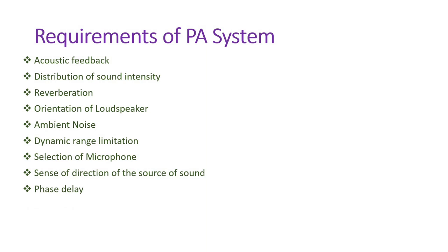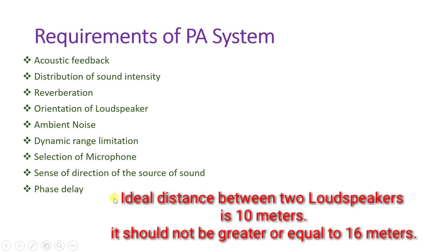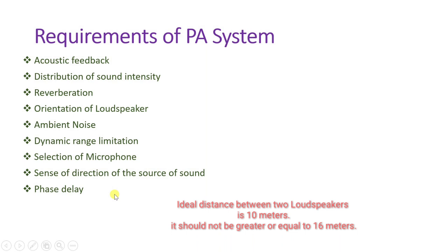Next is phase delay. Sound from the nearest loudspeaker may be heard together with sound from a loudspeaker at a greater distance, causing phase delay between the two sounds. To avoid this, loudspeaker separation distance should not exceed 16 meters. The ideal distance between two loudspeakers is 10 meters — exceeding 16 meters will start to create phase delay problems.